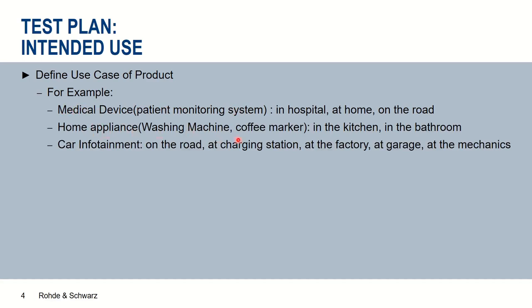For home appliances like washing machines and coffee makers placed in kitchens or bathrooms, they see a much more stable, time-invariant RF spectrum — not nearly as messy as a hospital environment. Cars and car infotainment systems encounter different scenarios and different RF spectra in real-world operation. The type of RF environment we observe needs to be reflected in our test approach and recreated in the lab.